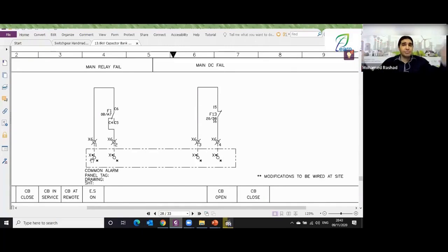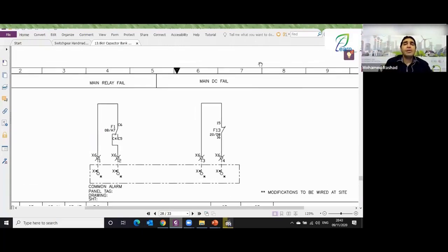Oh, sorry, it's called the protection room. It's called the common alarm panel, which is the unified alarm cell that contains things that couldn't be transferred via the BCU. Among them is the DC supervision on the protection relay circuit. Okay, I will find next to it a relay, and we will find the difference between this and that.